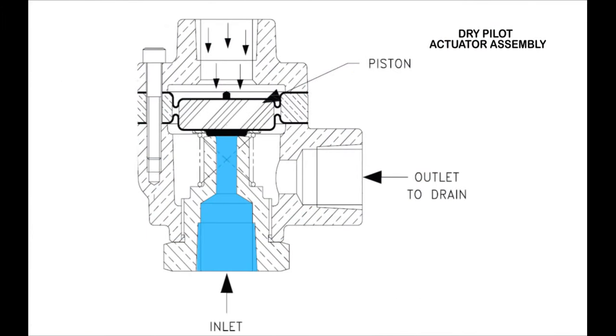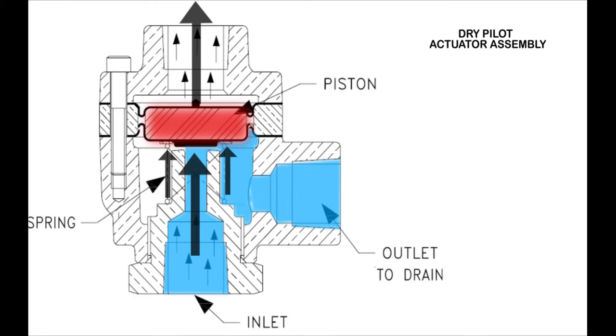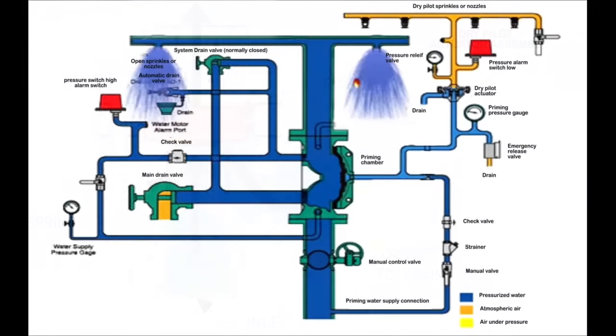Here is a diagram explaining the operation of the dry pilot actuator. In the shown figure, the valve is in the closed position, where pressurized air on the piston and diaphragm assembly works as a seal between the inlet and the outlet of the valve. When activated, the pressurized air above the piston is released. Therefore, the water pressure together with the spring force pushes the piston and diaphragm assembly upwards, allowing water to pass from the inlet to the outlet drain, consequently depressurizing the priming chamber pressure and activating the deluge system.